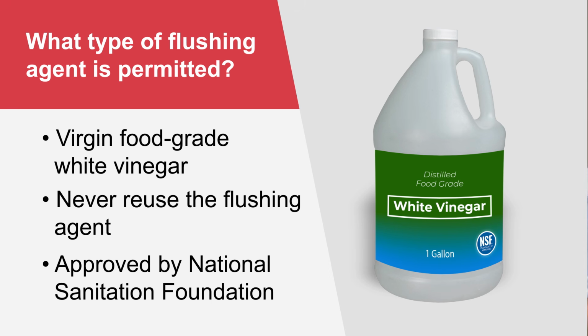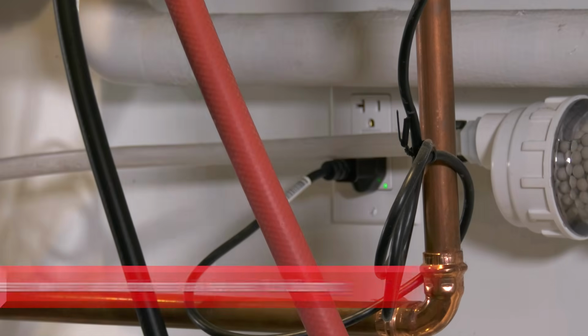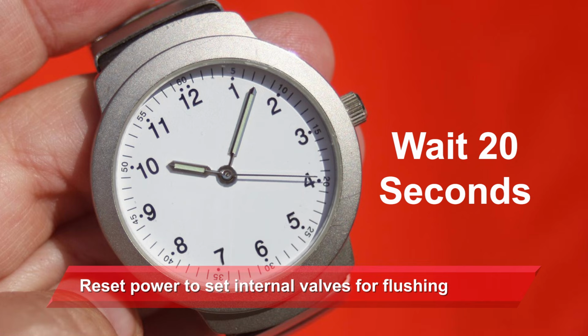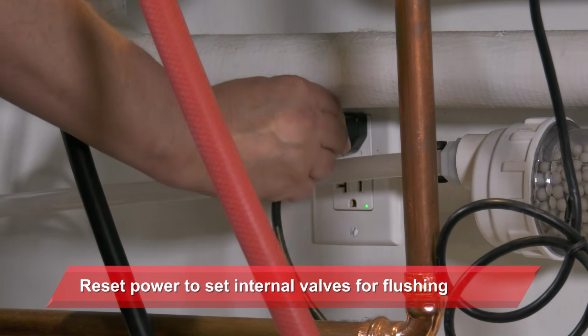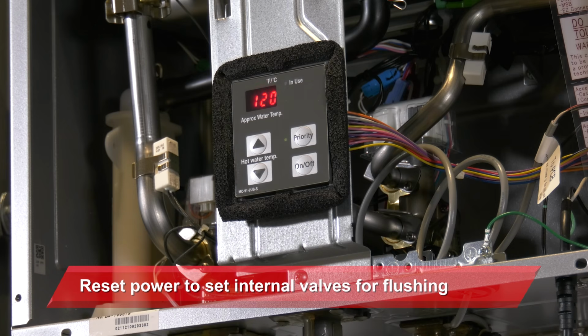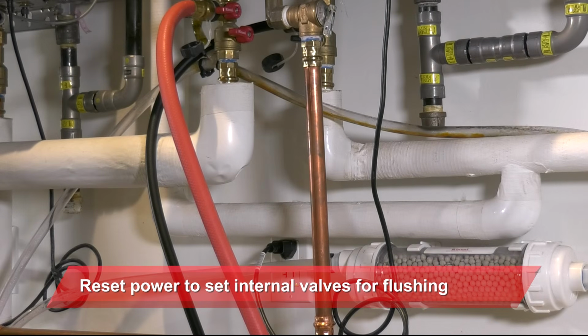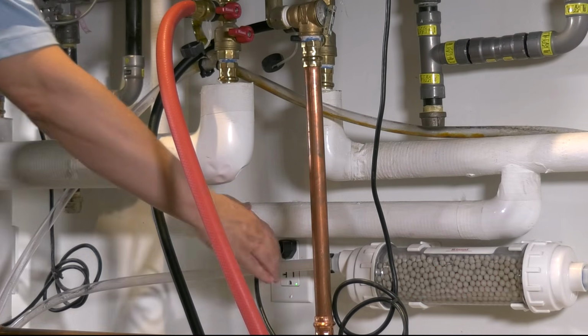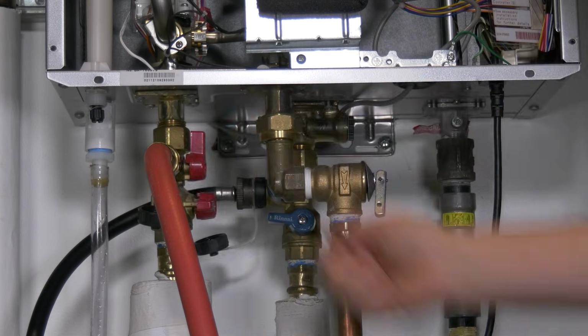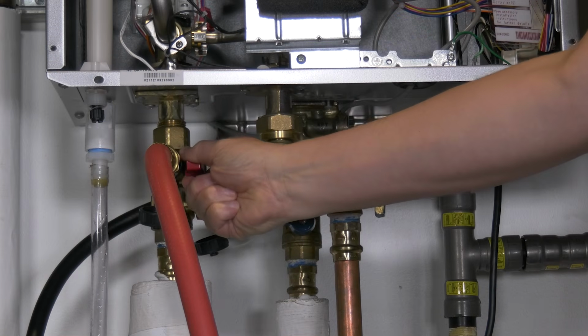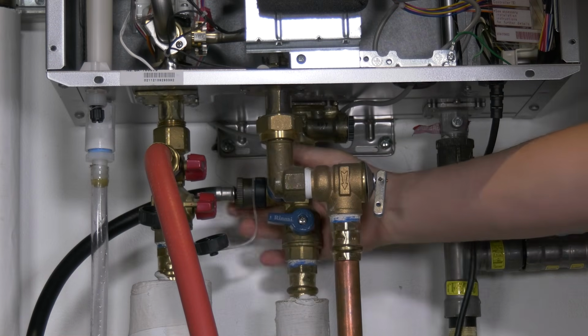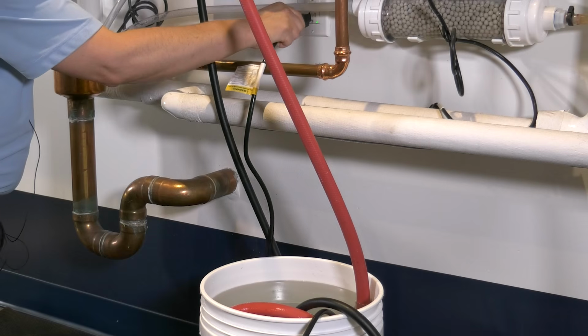Just before we start flushing, we want to remove power to the water heater being flushed, wait about 20 seconds, and plug it in again for about 20 seconds. Now, that faint rumbling noise is the internal water flow valves resetting to their default positions. This ensures an optimal amount of flow moves through the heat exchanger. Now, unplug the water heater a final time before starting the flush routine.